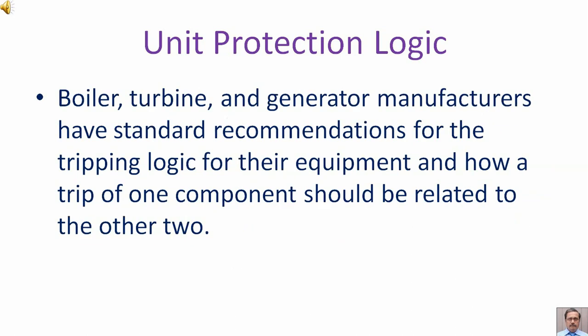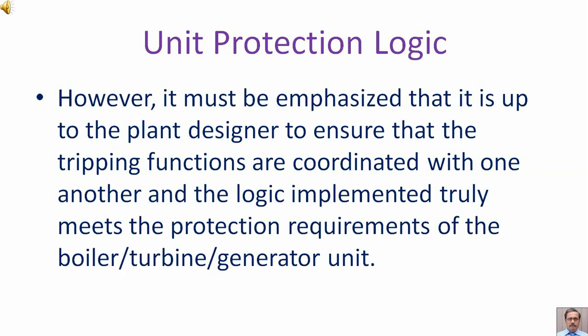Boiler, turbine, and generator manufacturers have standard recommendations for the tripping logic for their equipment and how a trip of one component should be related to the other. However, it must be emphasized that it is up to the plant designer to ensure that the tripping functions are coordinated with one another and the logic implemented truly meets the protection requirements of the boiler-turbine-generator unit.